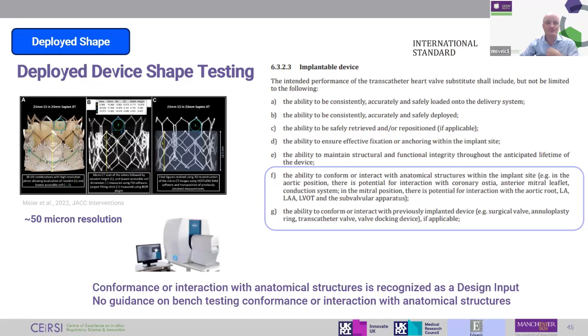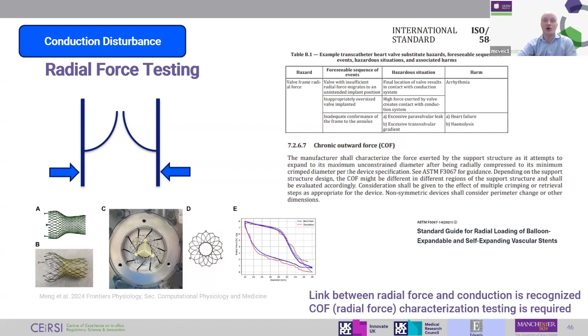Radial force testing is discussed in the standard pretty extensively, and it also says that high frame radial force is given as an example of a hazard that's mechanistically related to conduction disturbance. So that links radial force to conduction disturbance. The good news is we do have a test for radial force, and you could theorize that local radial force may be a predictor for conduction disturbance. And that's important because there isn't a test described or prescribed in ISO 5840 to directly address conduction disturbance or to measure contact pressure. If we go to the next slide, we'll talk a little bit more about conduction disturbance.